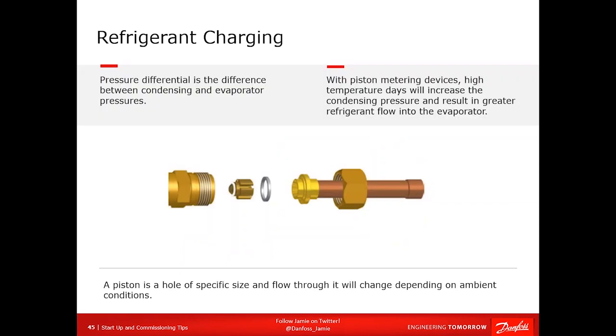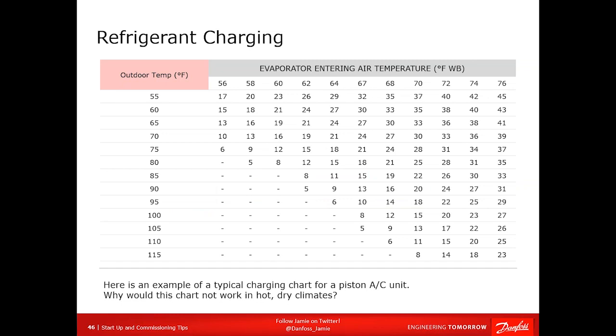For pistons, charge the superheat. A piston is basically a hole. How much flows through it depends on the pressure difference across it. So as you add refrigerant, the pressure difference increases, putting more flow in. The same happens with a change in outdoor temperature. So here you have indoor wet bulb, outdoor dry bulb. Notice for a given wet bulb, your superheat decreases for an increase in outdoor temperatures. So in this case, this is designed for relatively humid areas. You couldn't use this in Arizona because where you see those flat lines means you have a dead compressor. You have no superheat and you have flooding of a compressor.